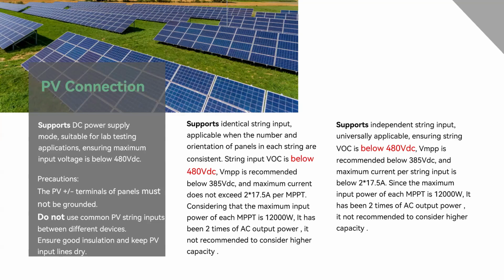We support two different ways of string input, identical string input and independent string input. As for the identical string input, it is applicable when the number and the orientation of the panels in each string are consistent, and the string input voltage is below 480 volts.